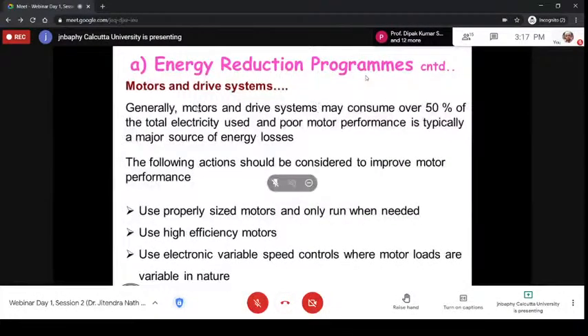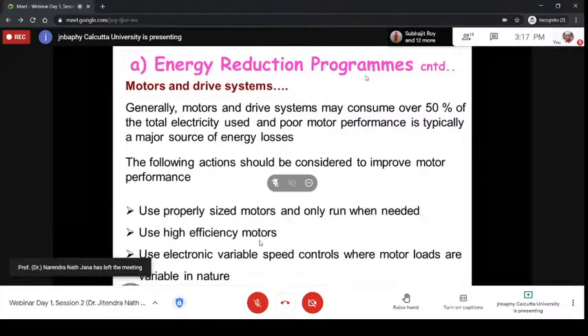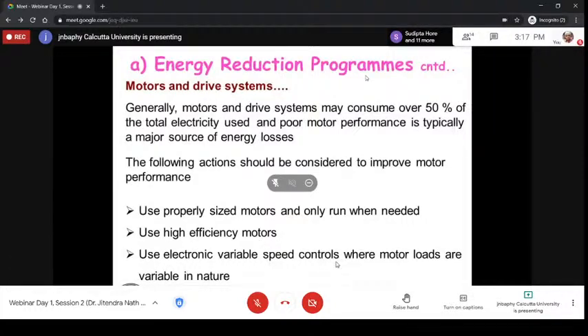Motor and drive systems may consume 50% of total electricity, and poor motor performance is typically a major source of energy losses. So use properly sized motors and only run them when needed. Use high efficiency motors and electronic variable speed controllers, rather than conventional ones, where motor loads are variable in nature.